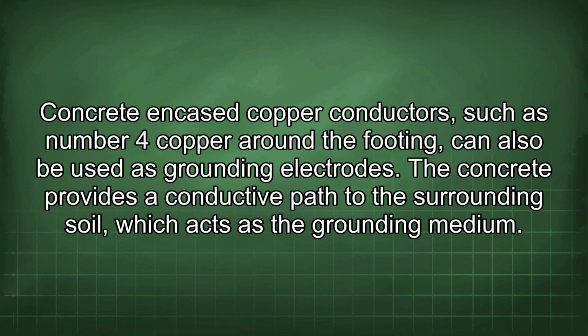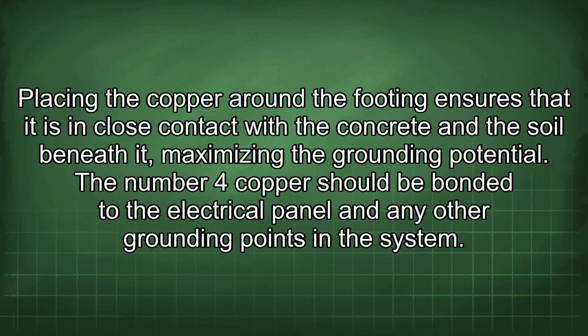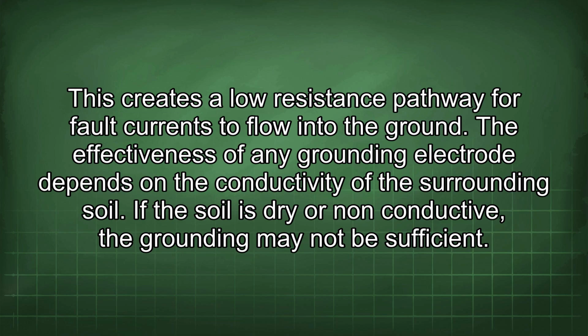The concrete provides a conductive path to the surrounding soil, which acts as the grounding medium. Placing the copper around the footing ensures that it is in close contact with the concrete and the soil beneath it, maximizing the grounding potential. The number 4 copper should be bonded to the electrical panel and any other grounding points in the system. This creates a low resistance pathway for fault currents to flow into the ground.